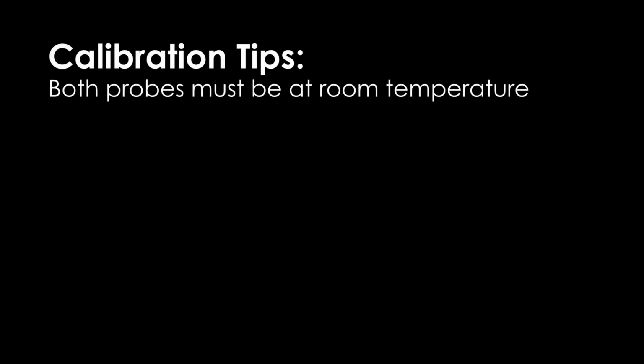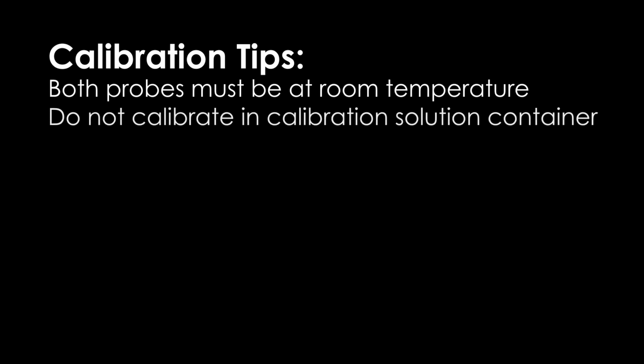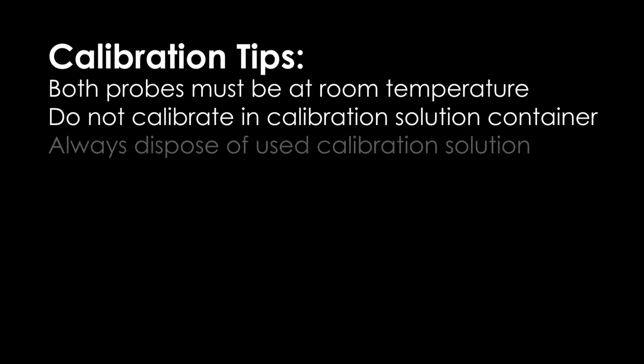First, the EC probe also features a temperature sensor. Both probes and the calibration solutions should be at room temperature before calibration. Do not calibrate your probe directly in the container of calibration solution, as this will change the chemistry and reliability of the solution. Instead, pour just enough solution into a small container, such as a shot glass or small water glass. Finally, always dispose of used calibration solutions.